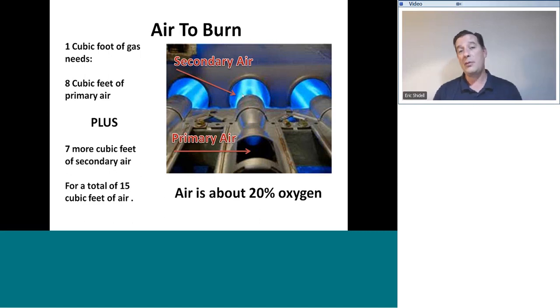So as a result, we need a baseline of at least 15 cubic feet of air for every cubic foot of gas that we are going to burn. Remember from before, what is the caloric value of natural gas per cubic foot? How many BTU will be released when 1 cubic foot of gas is burned? I'll answer for you. Remember, it was about 1,000 BTU per cubic foot.